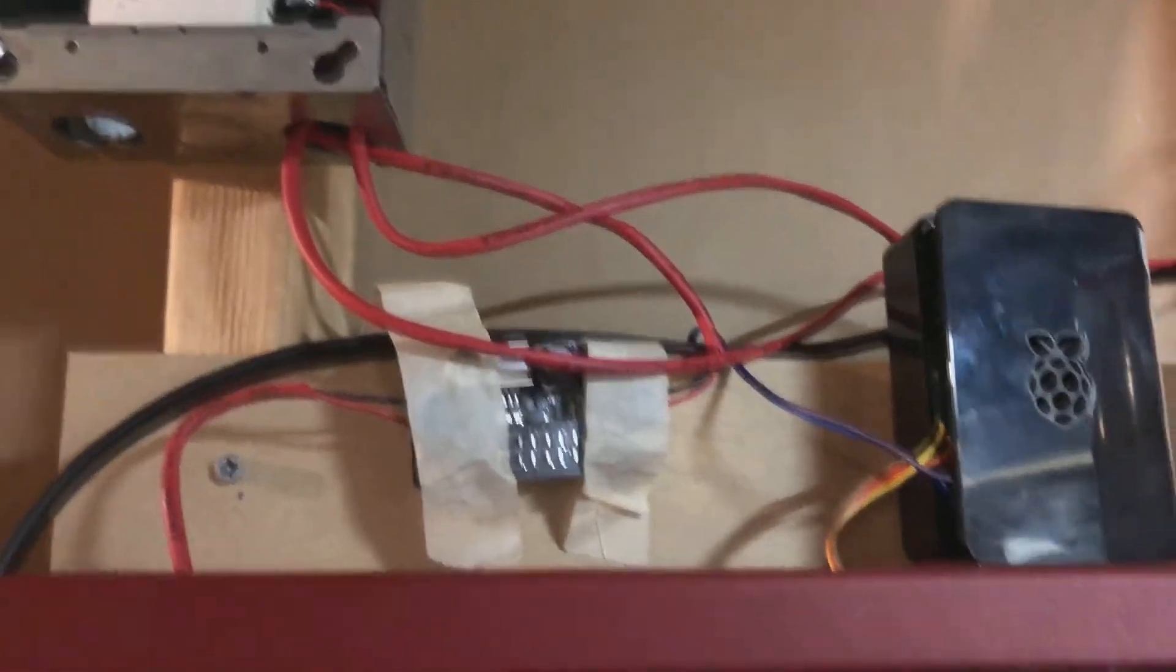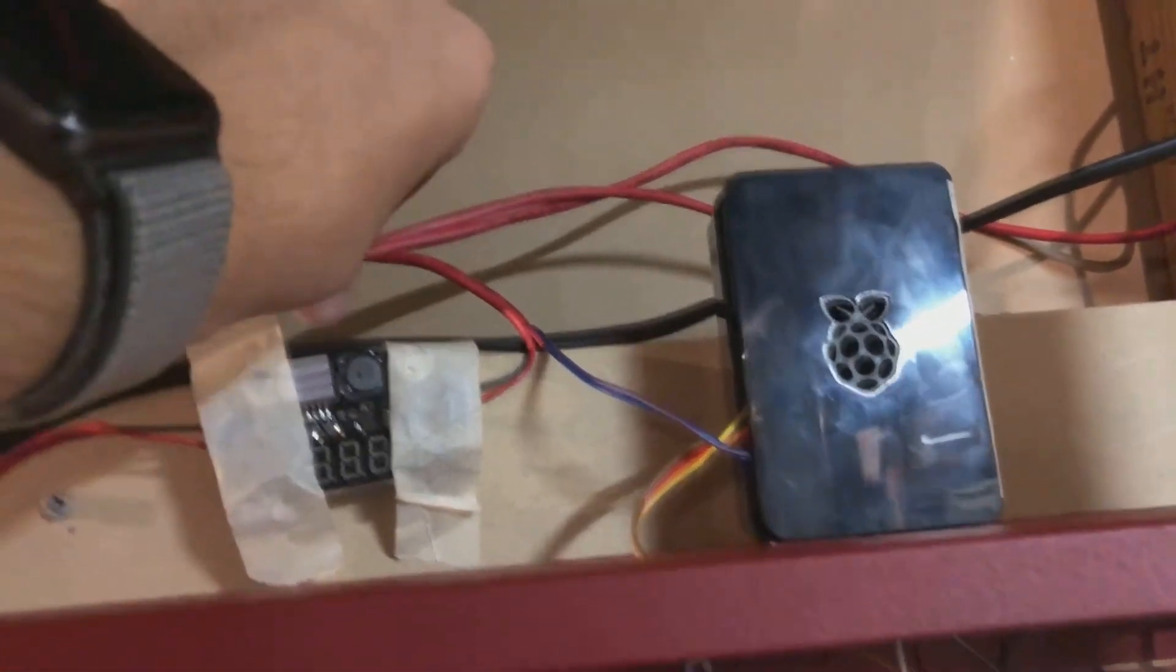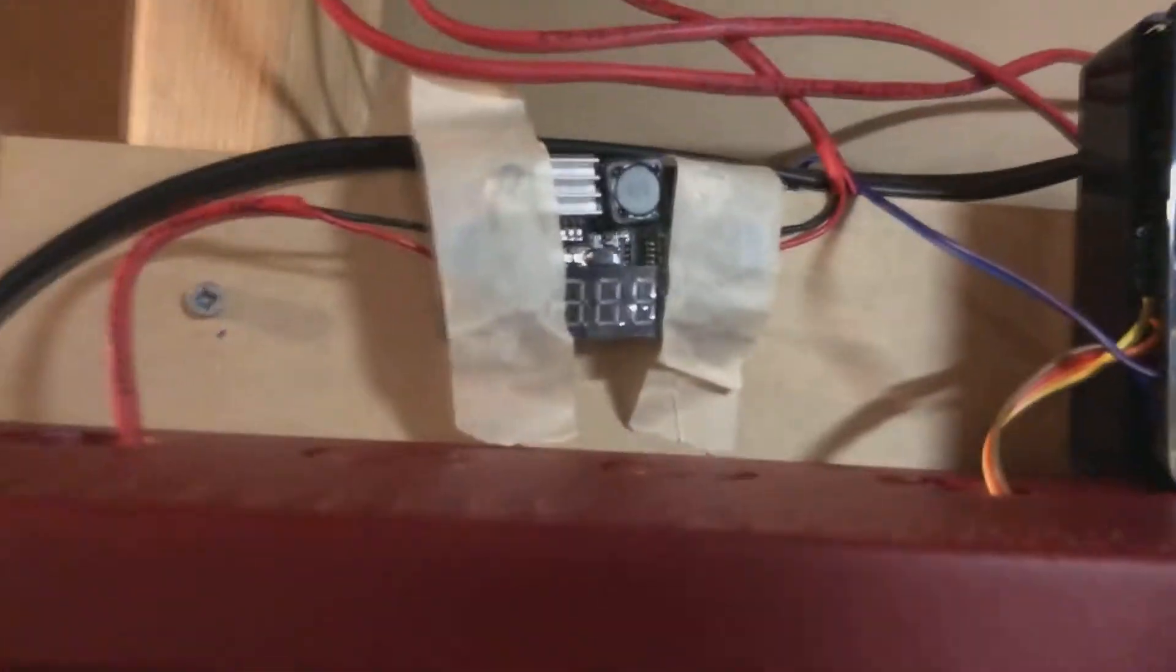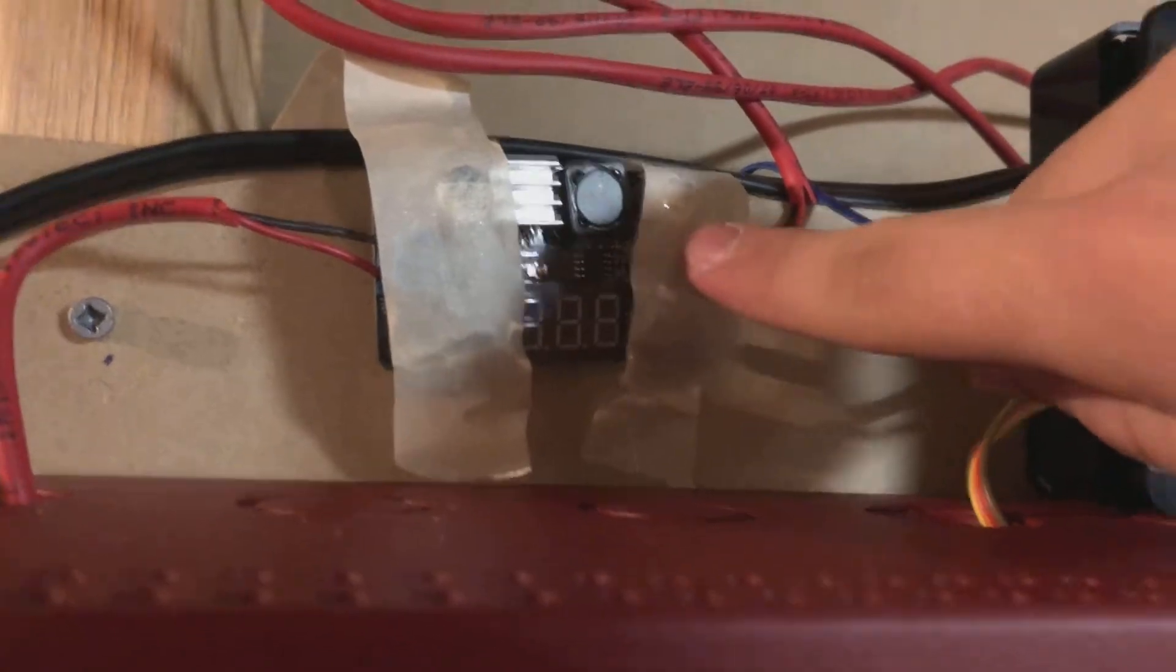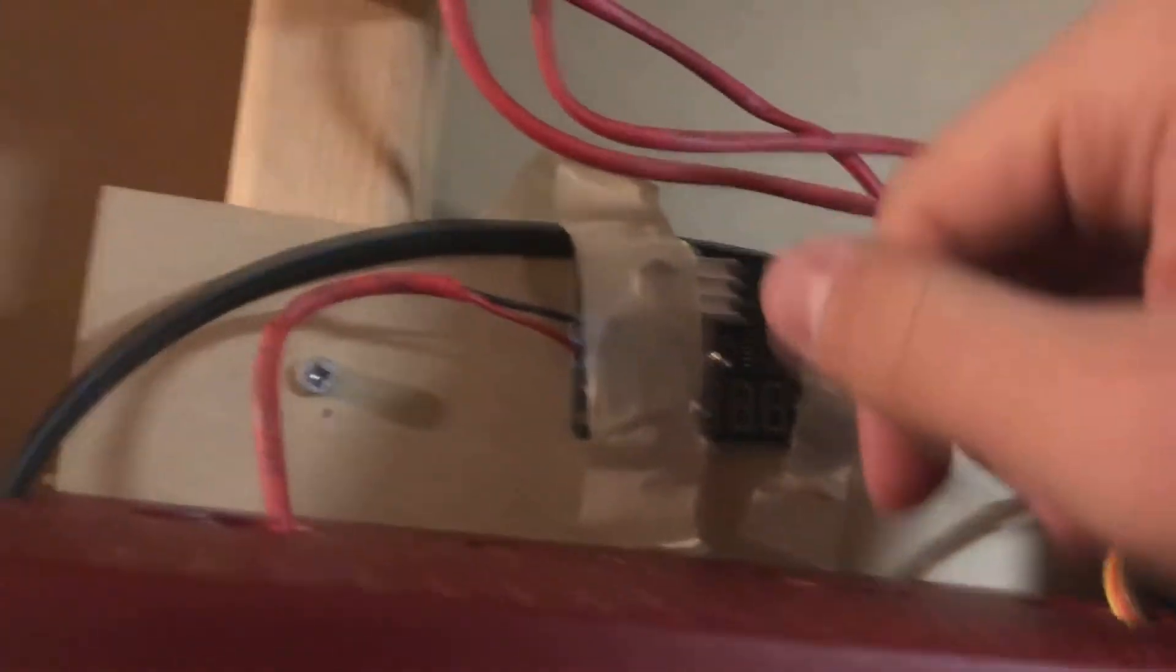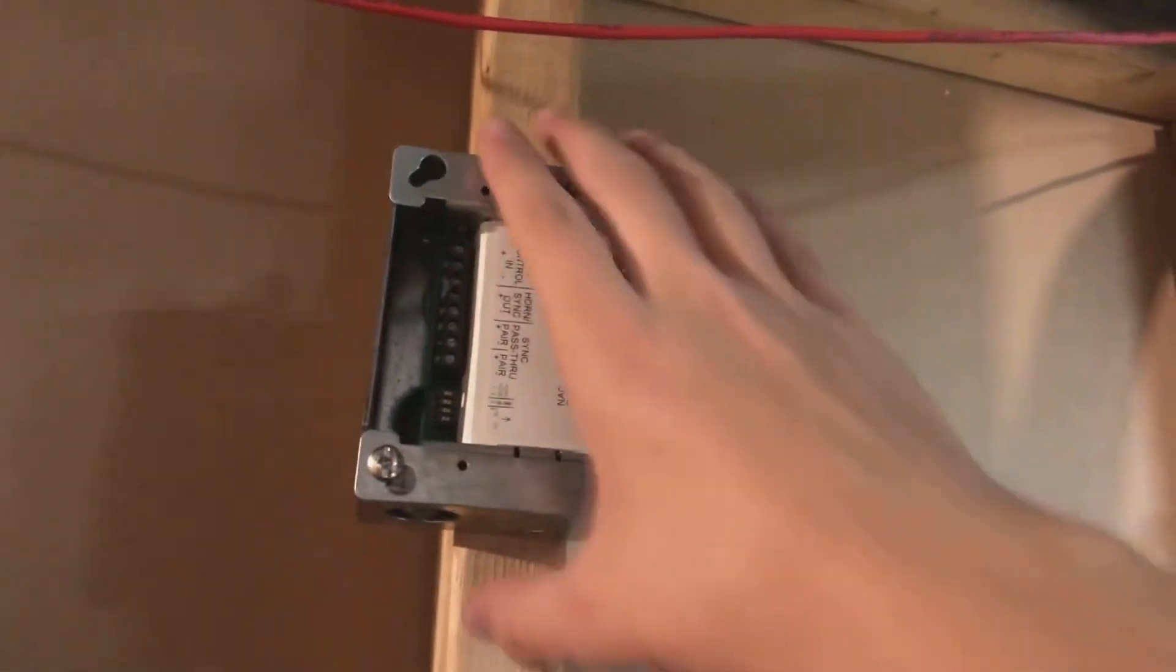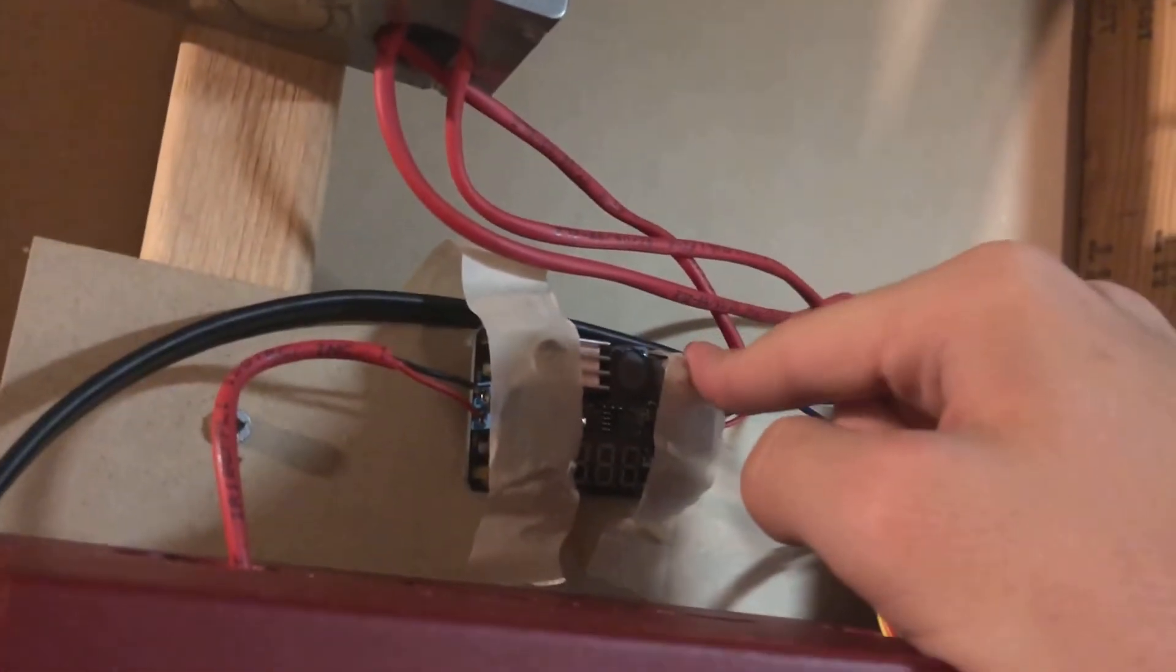Here, well this is so great - everyone likes these Simplex devices, why doesn't everyone do this, right? And when they go through panel upgrades and stuff, why do they have so many problems, why do they have to replace their devices still? What's - because of this. This guy right here. Unfortunately, due to the way this guy works, it doesn't like supervision current. In order for me to keep the panel normal, I have to keep my resistor here. Also this isn't the UL listed way of doing this - obviously masking tape isn't, but even if this could be in a junction box, NFPA would be like no. So though this works and I did sync up these devices, you know, that's why - this is why this can't be done in the field unfortunately, to my knowledge anyway. And it's because of this, this DC to DC filter.